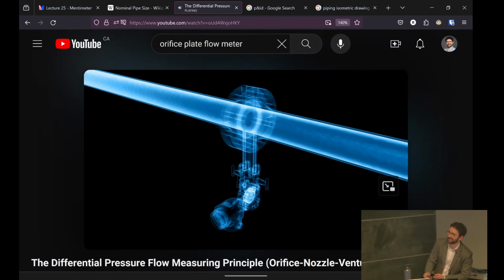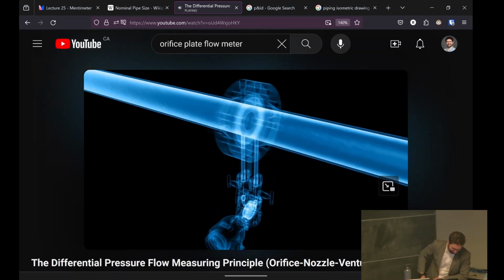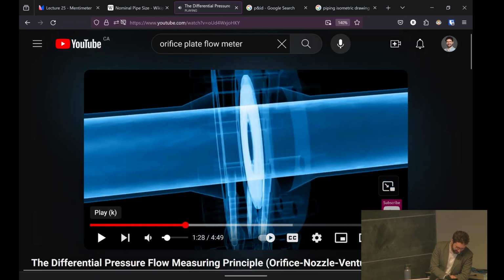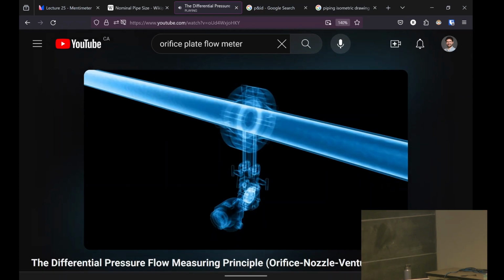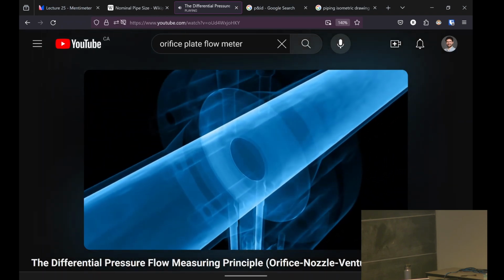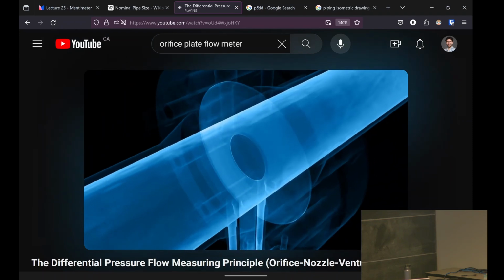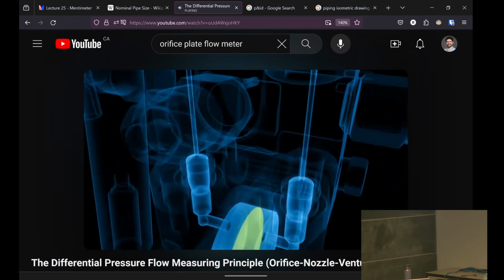Here's how this measurement method works. Differential pressure flow meters have an artificial restriction. So this is an integrated orifice plate. It's a really small device. This whole thing is a little flange, and there's a differential pressure gauge with pressure taps going on each side of the integrated orifice plate into the measuring tube. Two separate tubes connect these holes to a differential pressure sensor with its two pressure chambers separated by a diaphragm.